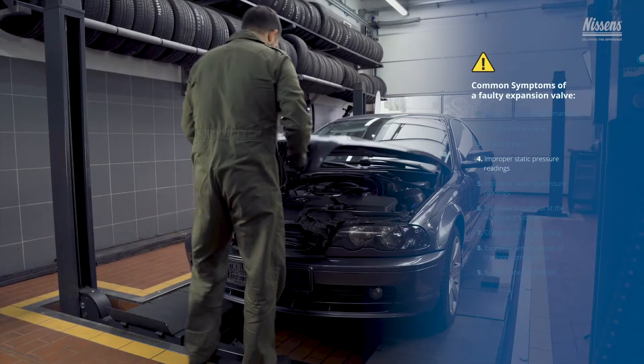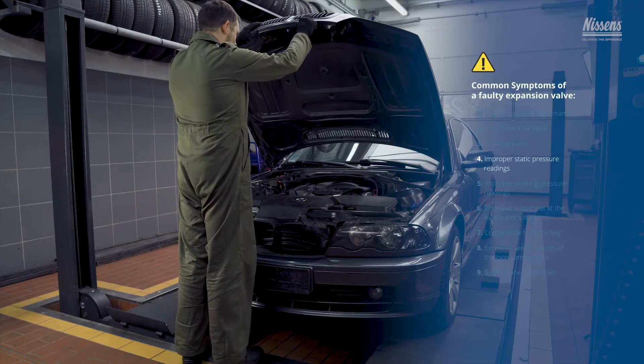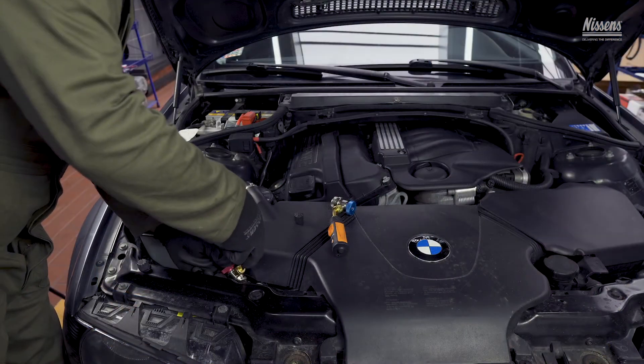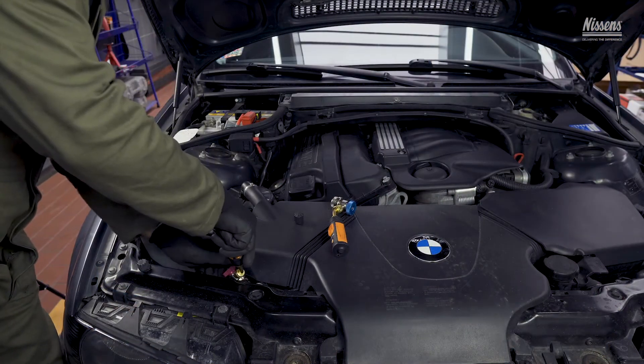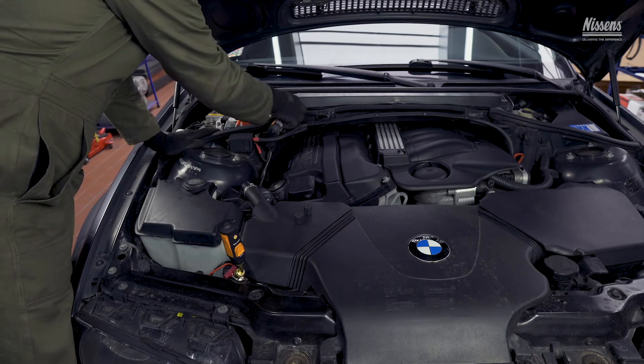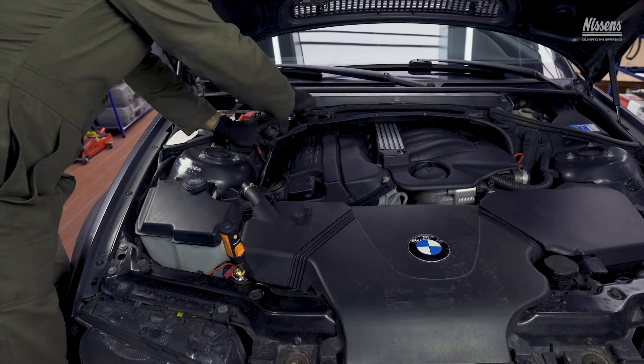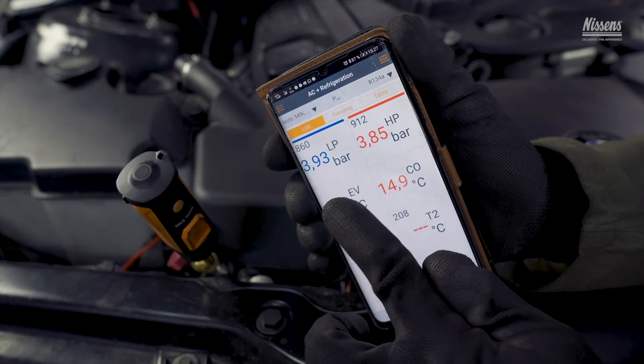Improper static pressure readings: if the high-pressure and low-pressure side readings do not equalize when the system is off, system clogs may be the reason, and the TXV is one of the potential spots where they occur.